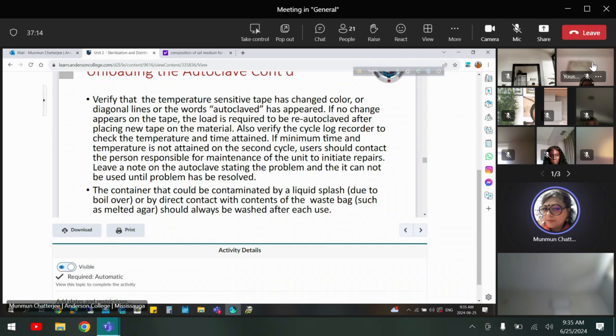Also verify the cycle log recorder to check the temperature and time attained. So you can see whether you should stay there until the pressure and the temperature have been reached. But anyway, you have to check everything, whether the temperature has been attained at that time. Otherwise, why didn't it get autoclaved? If minimum time and temperature are not attained on the second cycle, the user should contact the person responsible for maintenance.